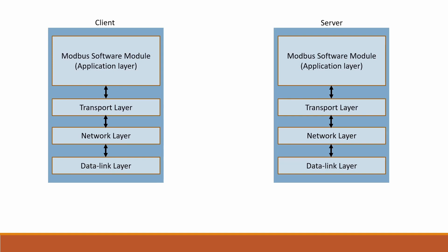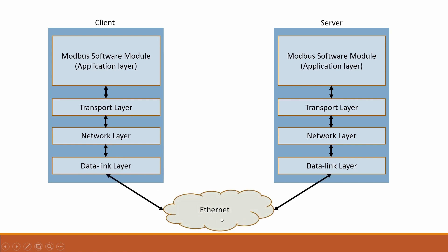Coming to the Modbus network layering, there are five layers: the Modbus application layer, the transport layer, the network layer, the data link layer, and finally the physical layer, which is Ethernet. There is no presentation layer or session layer here because Modbus does not support data encryption, decryption, authentication, or authorization services. Both the Modbus client and the Modbus server allow data flow in both directions.